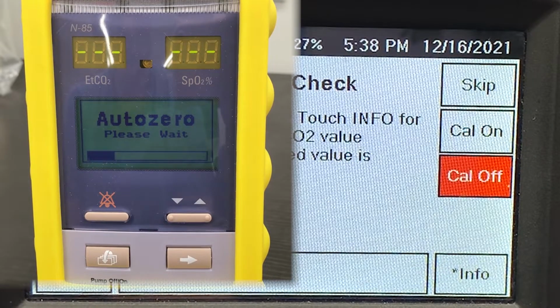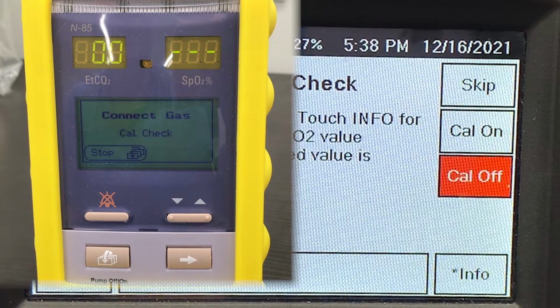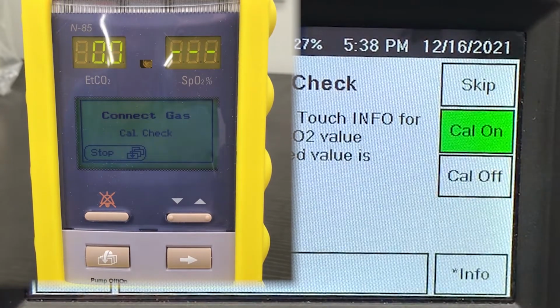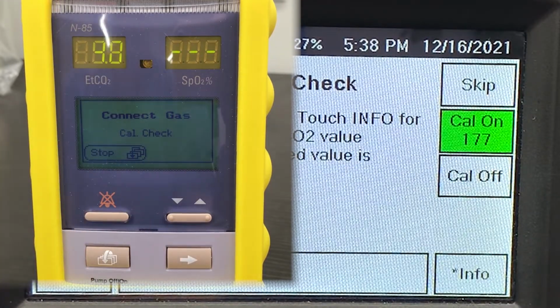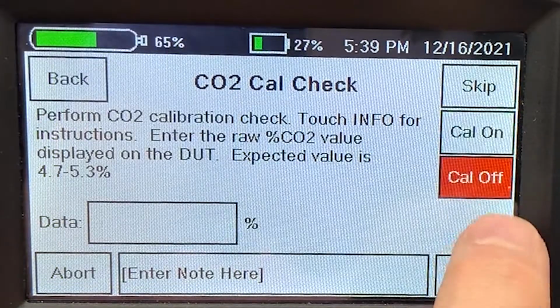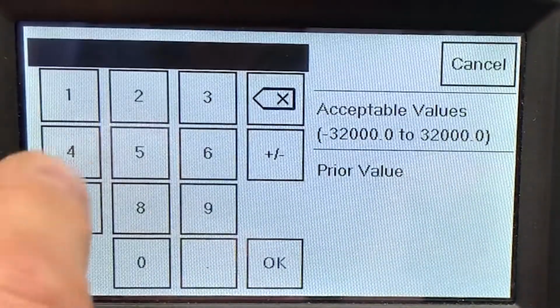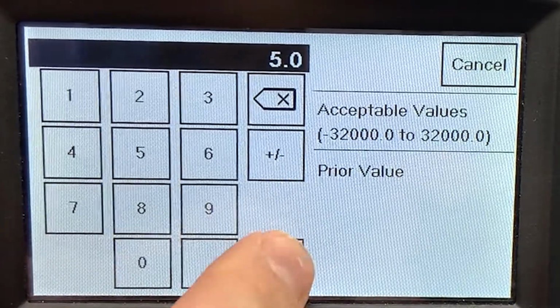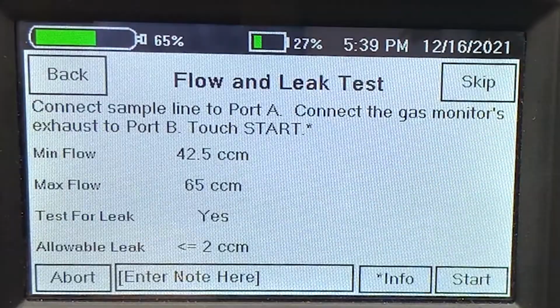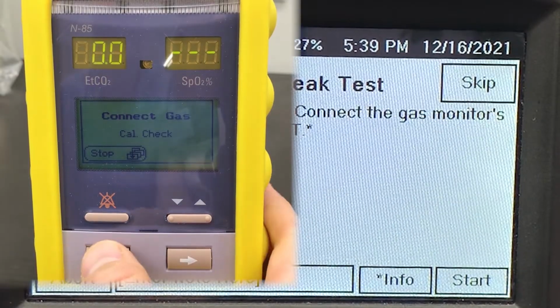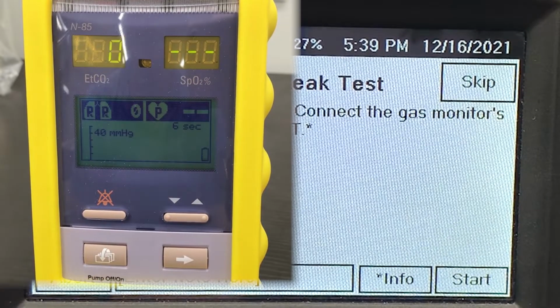After running the calibration, not everybody will do this second test. They'll just assume that it's 5% because, you know, when you calibrate it, that's what it sets itself to. But when you do this cal check, it doesn't always read exactly 5%. It's usually plus or minus a tenth. So now we can touch cal on the smart tank. Watch this value. 4.9, 5.0. So we can turn the cal gas off now. Say next. We can exit out of this, and it will exit back to the normal mode.